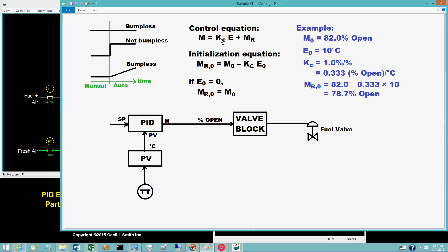Initialization of a PID block derives from the proportional plus bias equation: m equals k sub c times e plus m sub r. This equation is solved for m sub r and evaluated at the time the block is switched to auto, designated as time 0. The result is: m sub r at time 0 equals m at time 0 minus gain times error at time 0.